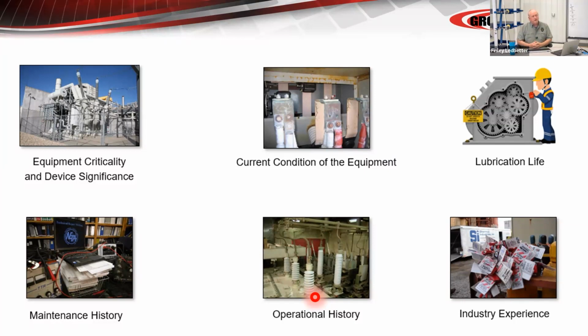We ran into a power plant in Central Texas a few years ago. They started having breaker failures at about 3,000 operations. Yet they had 8 or 10 out of 80 breakers with 3,000 or 4,000 operations on them, and the rest of their breakers had about 100. Maybe during maintenance, someone should have suggested they take these 3,000 operation breakers and put them into non-critical circuits, and move some of these breakers with only 100, 200 operations onto these repetitive duty critical circuits. That's the sort of simple thing that'll make a difference.